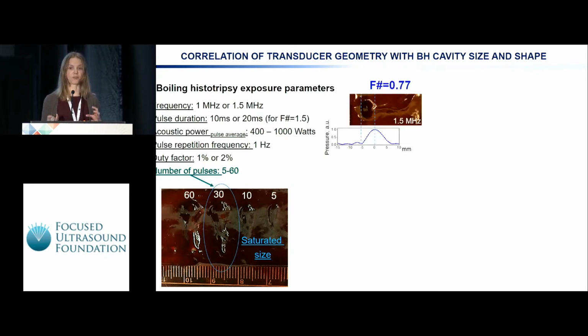So if we take the most focused transducer and make a cavity using that at 1.5 megahertz, the growth of the cavity axially stops exactly at the first null of pressure distribution. If we operate that transducer at 1 megahertz, it becomes exactly 1.5 times larger than at 1.5 megahertz. So it scales with frequency in all dimensions, and it correlates quite well with the distribution of peak-to-peak pressure.